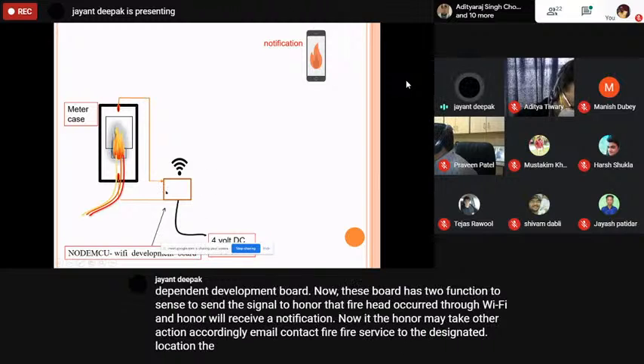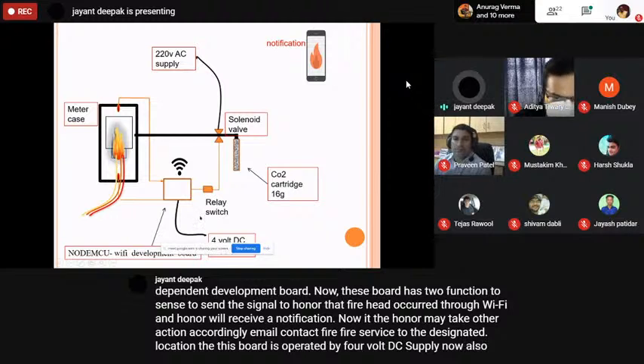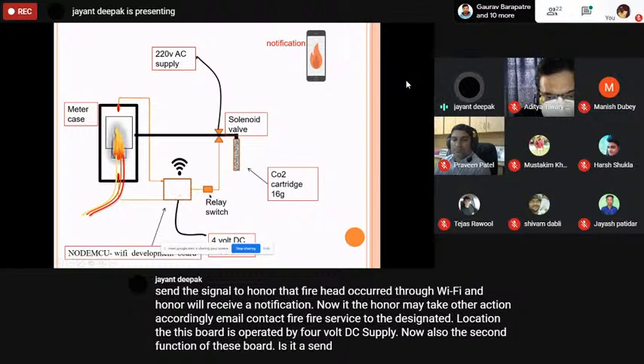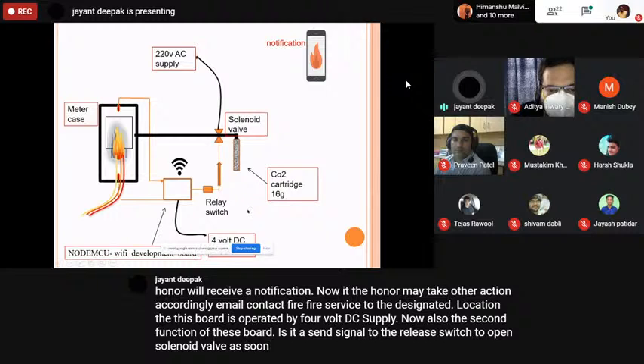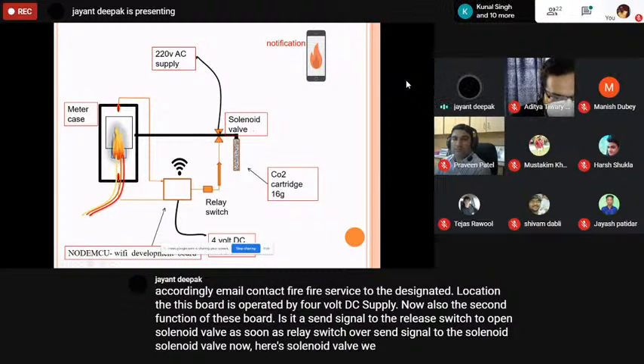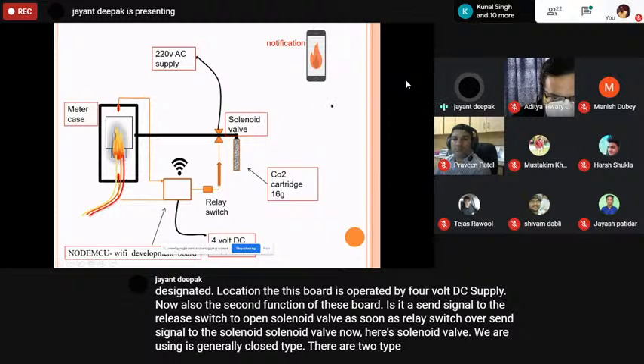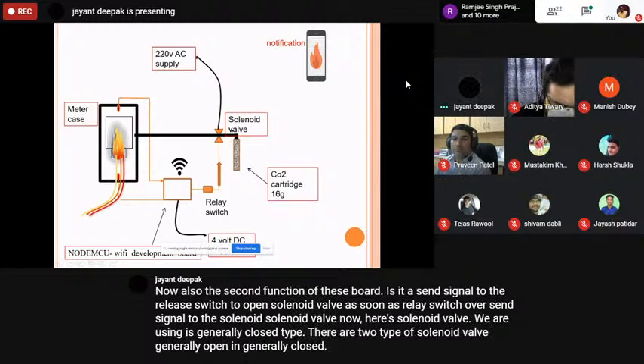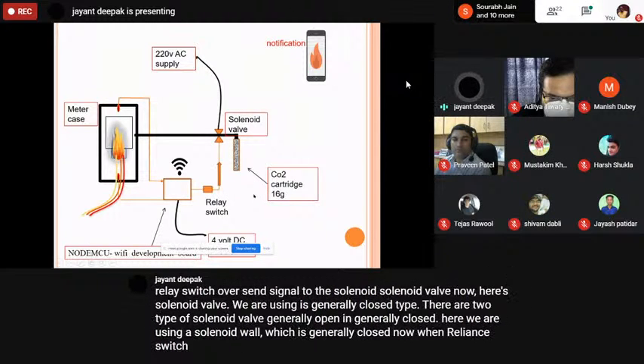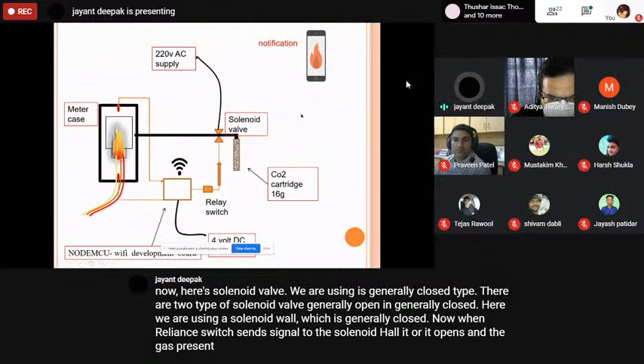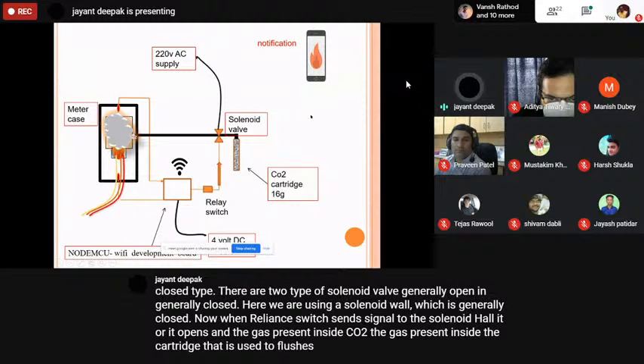This board is operated by a 4-volt DC supply. Now the second function of this board is that it sends a signal to the relay switch to open the solenoid valve. The solenoid valve we are using is generally closed type. There are two types of solenoid valve: generally open and generally closed. Here we are using a solenoid valve which is generally closed. Now when the relay switch sends a signal to the solenoid valve, it opens, and the gas present inside the cartridge, that is CO2, flushes inside the meter case and extinguishes the fire.